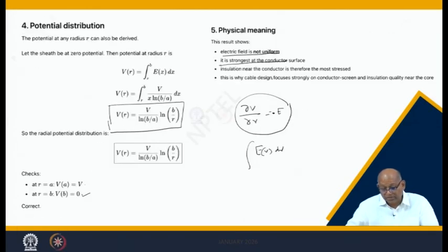All right. So this is how the insulation near the conductor is most stressed. This is why cable design focuses strongly on the conductor screen and insulation quality near the core. You have to be very careful near the core, where the insulation is touching the conductor inside.